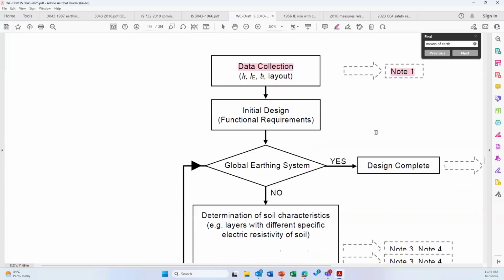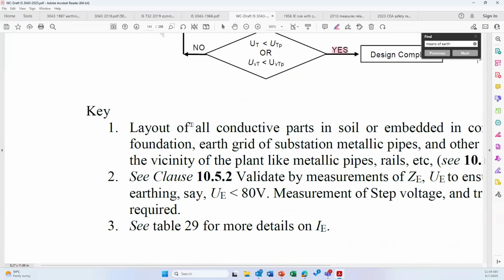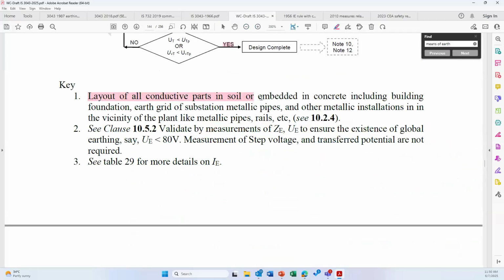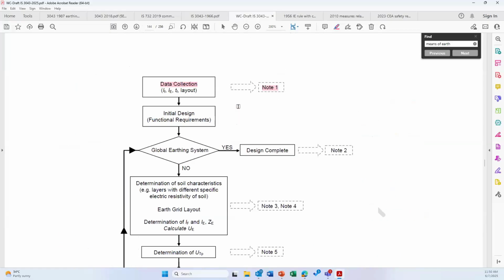We have put a note 1. Note 1 gives you information on what exactly we are talking about. Layout of all conductive parts in soil or embedded in concrete, including building foundations, earth grid of substation, metallic pipes, and other metallic installation in the vicinity of the plant, like metal pipes, rails, etc. So everything buried in soil or inside concrete has to be considered while calculating this particular layout. Then initial design, functional requirements.